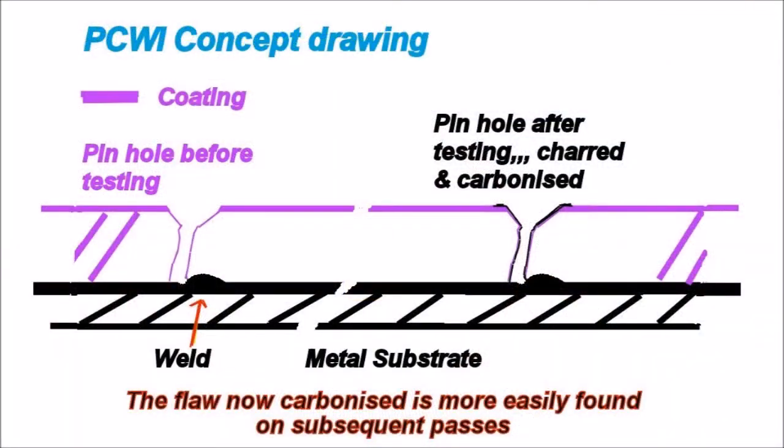We need to understand one thing. Once a pinhole has been tested and found, it chars and carbonizes. That means from the substrate, you get a black char which goes to the top of the coating. So it is very easy to find the second time and on subsequent passes. It's the initial flaw that's hard to find.